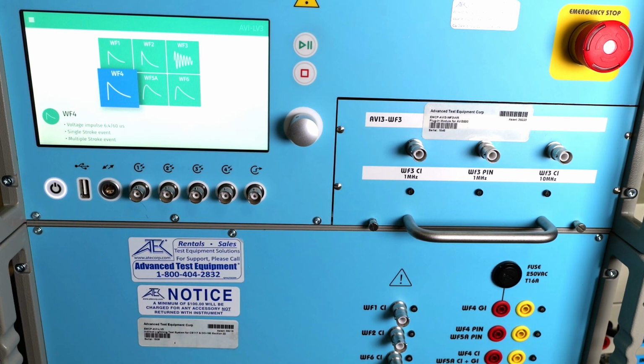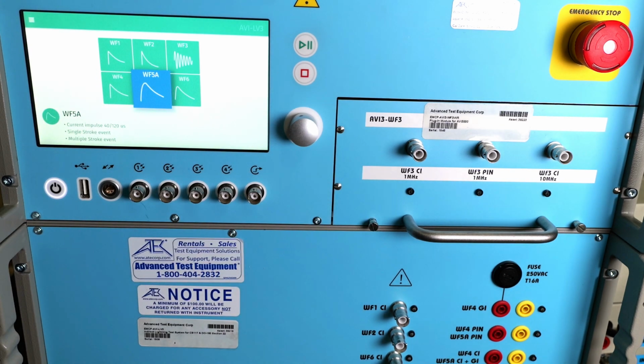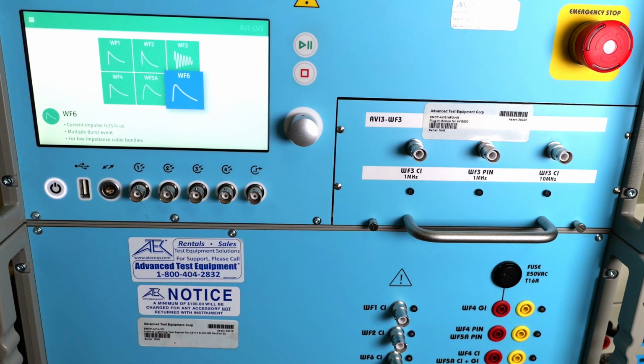For waveform 4, we have a voltage impulse of 6.4 by 69 microseconds, and that has a single stroke and a multiple stroke event. Waveform 5A is going to be current 40 by 120 microsecond, single stroke and multiple stroke. And finally, waveform 6 is a current impulse of 0.25 by 4 microseconds with a multiple burst event. Keep in mind, different impulses are going to have different outputs on the generator.